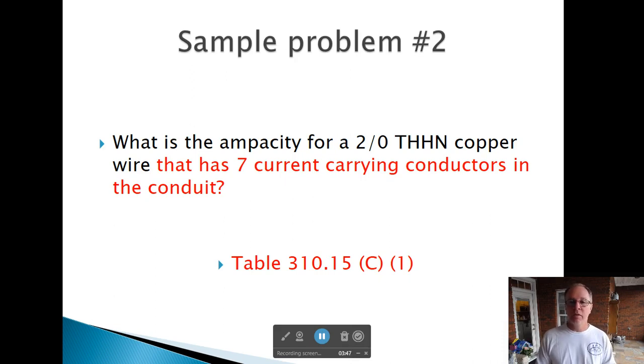What is the ampacity of a 2-Aught THHN copper wire that has seven current-carrying conductors in the conduit? We go to Table 310-16 and we find 2-Aught THHN copper, which we know is 195 amps. Then we go to Table 310-15-C1 to find out what we've got to do because we've got seven current-carrying wires in it.